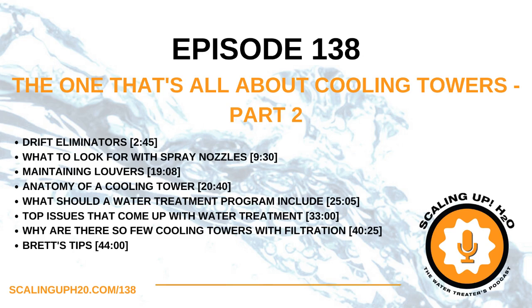So that's one thing we've kind of been educating the industry on: do not use 100% softened water to make up a unit with galvanized steel. You could split stream soften it, but it's a risk with that. You might be helping from the scaling perspective, but from the corrosion end, you're hurting the unit.